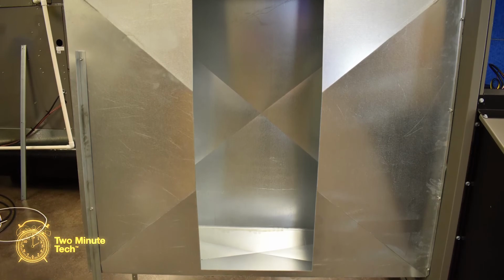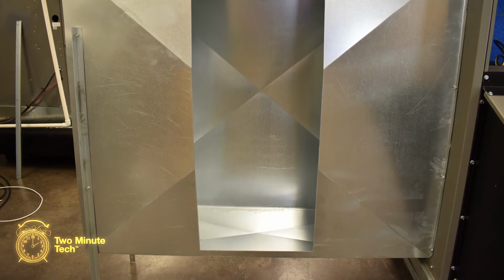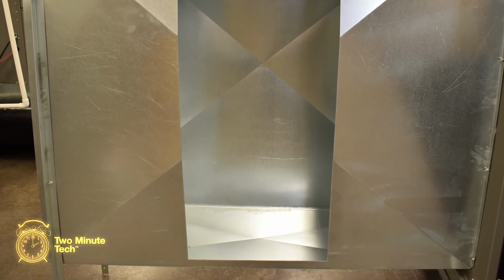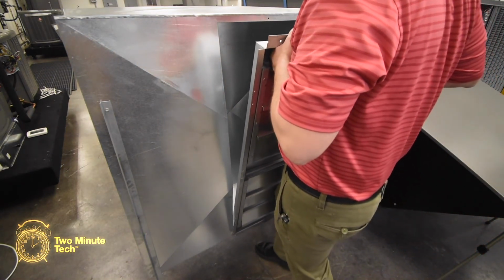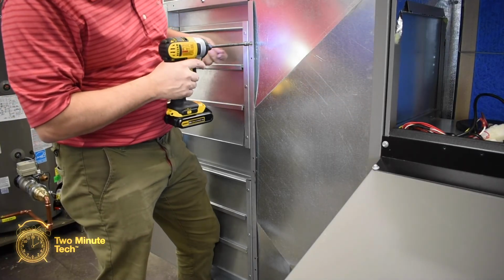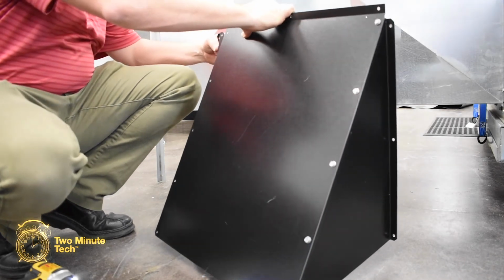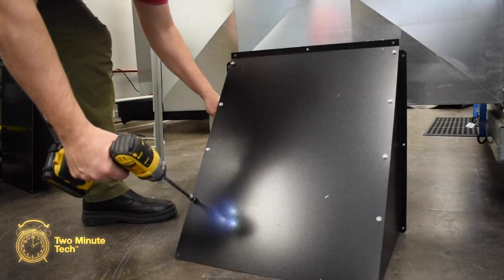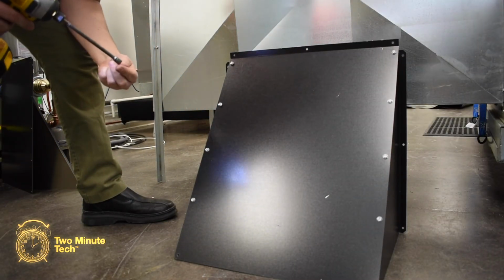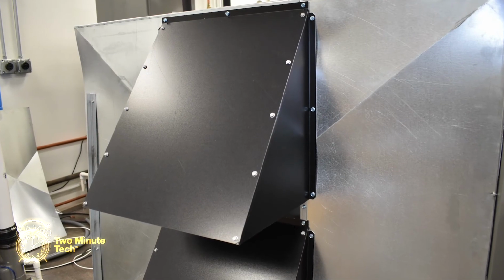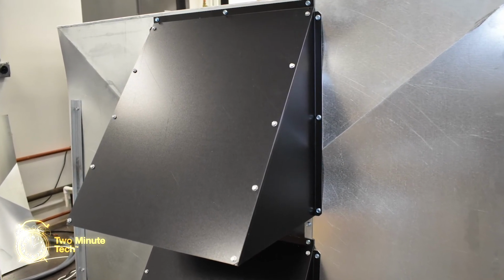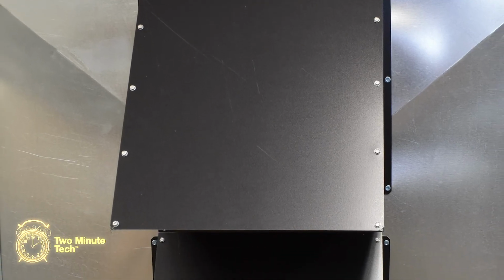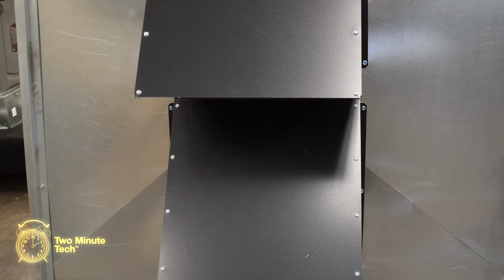Attach the ductwork to the side of the unit. Cut an opening in the side of the ductwork for the barometric relief assembly. Attach the barometric relief assembly to the horizontal ductwork. Assemble the 2 small barometric hoods. Attach the angled side panels to the hood panel. Attach the barometric hoods over the barometric damper assembly. Seal all joints and seams per industry best practices.